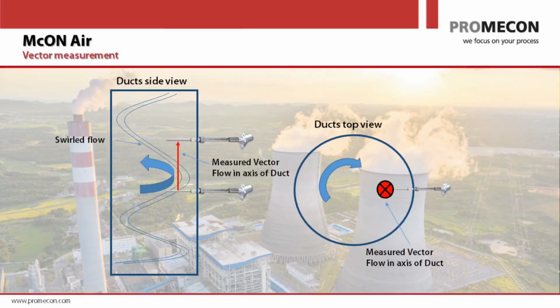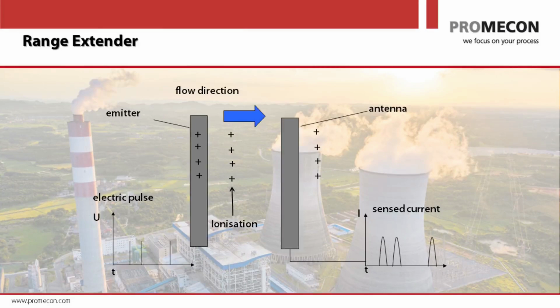Okay, so that's that. Another thing I would like to mention about the function of our system is what do we do if we have no dust? That's a frequent question that is asked. Let's say our system has no dust. So you purge a mill with cold air. The cold air has not been going through the air heater, and therefore there is not much dust in the air. For this, we have developed the so-called range extender.